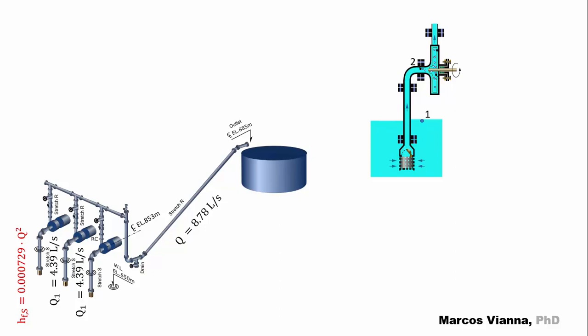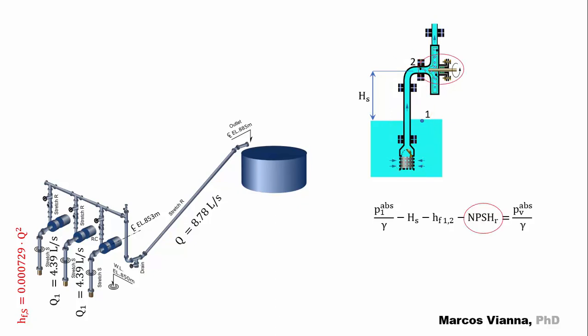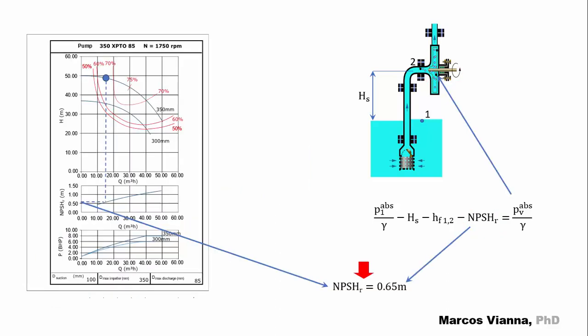Now, this is what happens at the suction of each pump. When we consider that the absolute head at the suction sump is imposed by the atmospheric pressure, and we subtract the static suction head and the suction head losses at the suction pipe and fittings, the required NPSH is the value of head that would make the head in the interior of the pump equal to the absolute vapor head. In other words, the available NPSH must be greater than the required NPSH, or cavitation will take place inside the pump. But as we said, there are cases in which we still don't have the pump chart — so what can we do then?